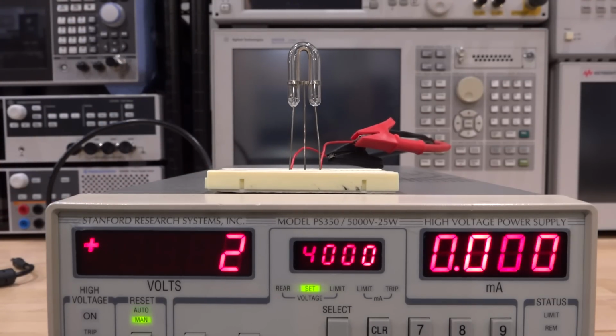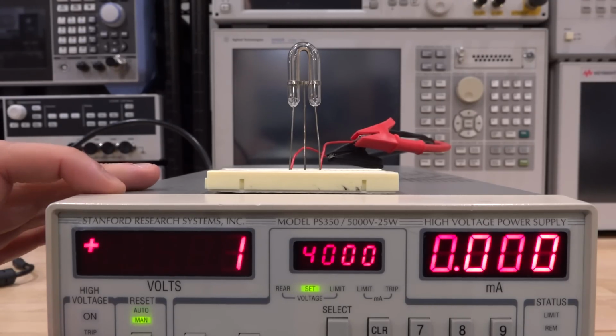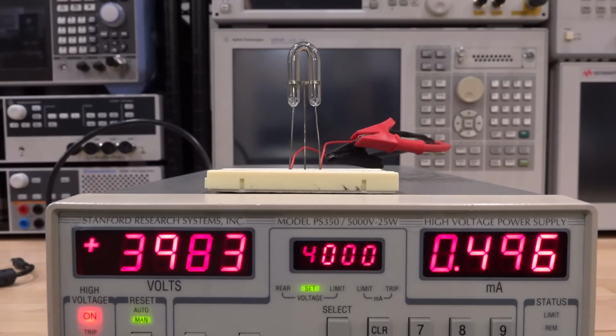So in this case, I'm going to apply 4,000 volts directly to the outside terminals. We're not going to use a 3rd terminal, and it will ionize by itself. The resistance will drop, and the power supply should protect us, I hope, in the case of this situation. Let's go and turn it on. And here we go. Look at that.